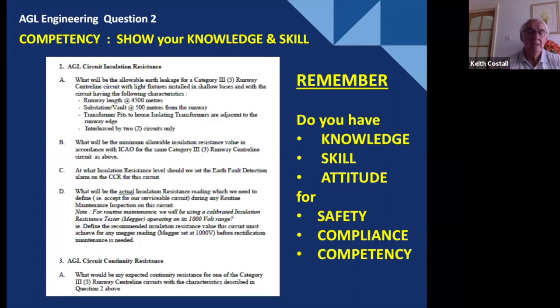So there's a consideration there. And the other aspect is that in ICAO standards, in the Aerodrome Design Manual Part 5, it calls for doing an insulation resistance check with a suitable insulation resistance tester, we commonly call the Megger test, because Megger was the first company to do an insulation resistance tester of the appropriate type. And ICAO called for us to do it at 5,000 volts.